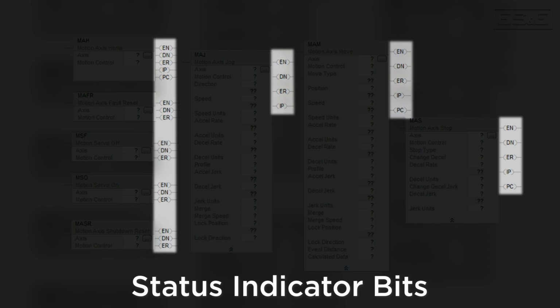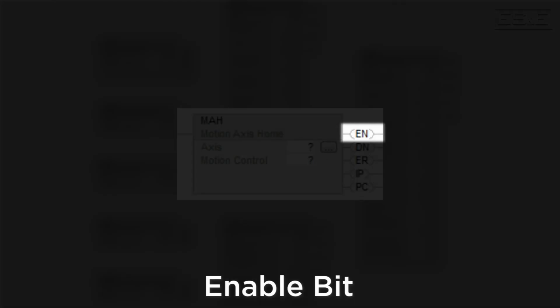Next, let's take a look at the status indicator bits. The status indicator bits don't tell you anything about the axis that's being targeted. They're just diagnostics for the instruction itself. The enable bit will turn on if the rung that the instruction is on goes true. This tells you that the instruction has been enabled, but not necessarily that it's executing. The enable bit stays on as long as the rung is true.